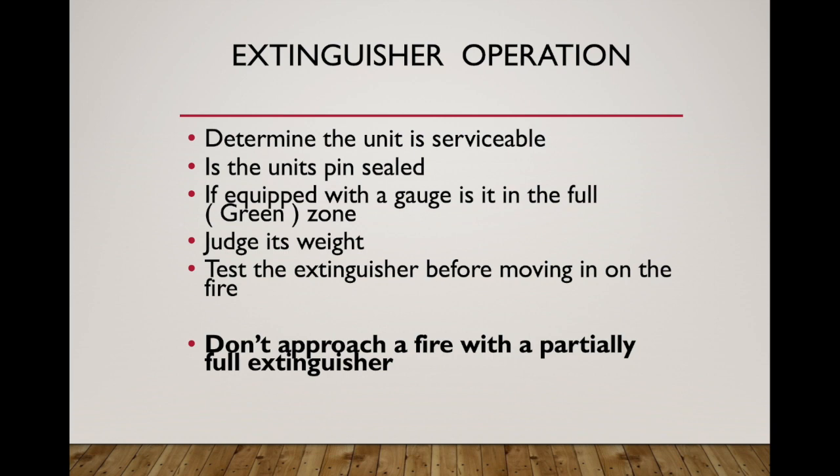Extinguisher operation. Before grabbing it off the fire truck, you once again want to verify that the unit is serviceable. So the extinguisher gauge is in the green, good to go. The pin was in place with the tamper seal, or if it was a CO2 extinguisher, that it has the appropriate weight. We don't want to grab an extinguisher that was partially discharged already prior to being used. This should be caught in our weekly checks of the apparatus and monthly checks of the station. Test the extinguisher before moving in on the fire.